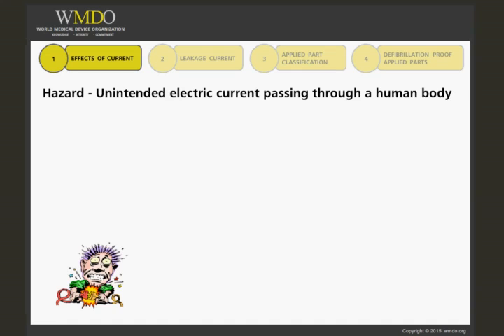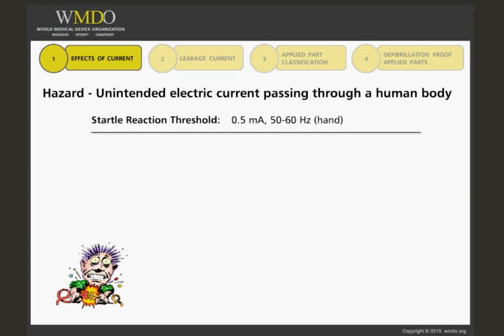Let's start by reviewing the reactions to different levels of current and frequency when a hazard occurs of unintended electrical current passing through a human body. First, we have the startle reaction threshold, which is caused by a current of 0.5 milliamps, 50 to 60 hertz, to the hand.